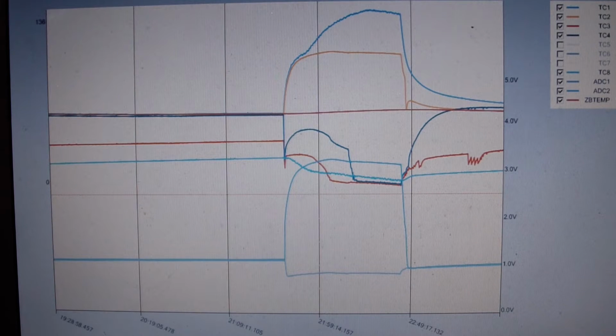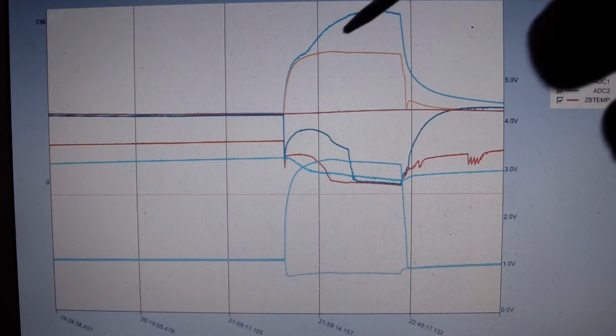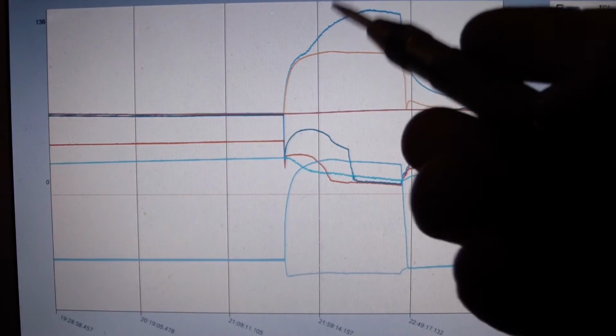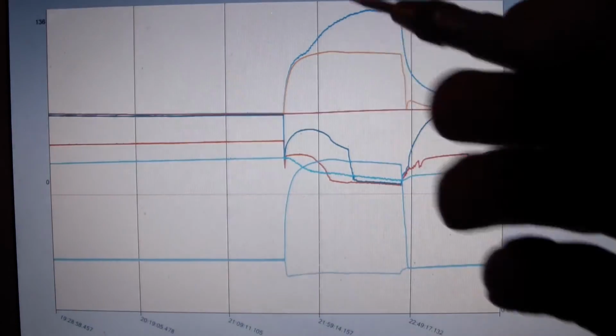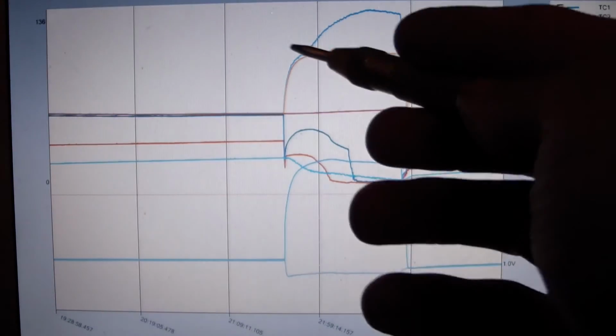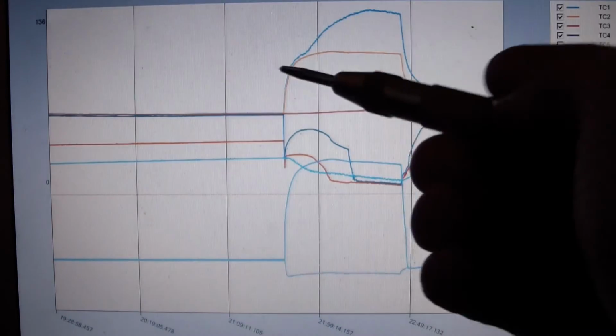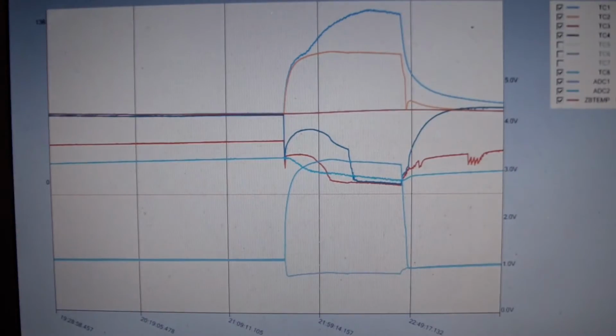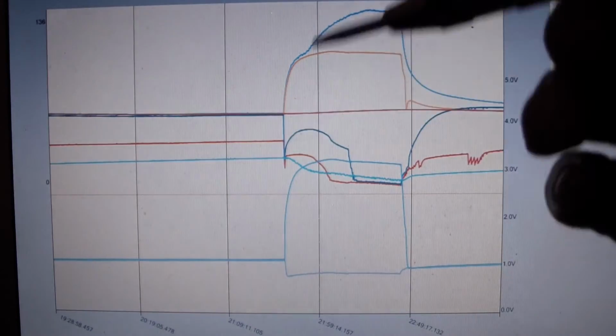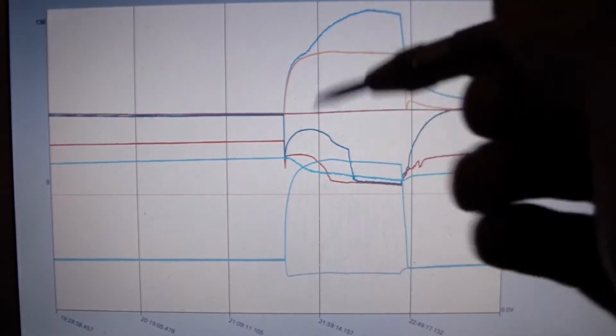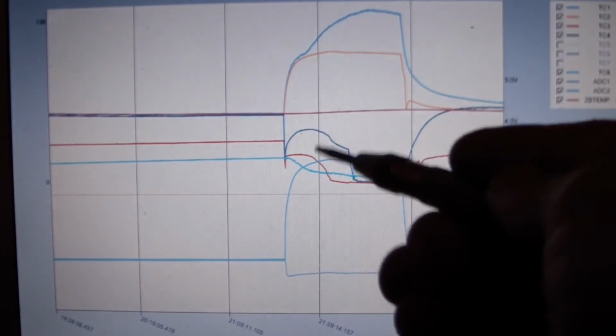I think that is probably the point where we're starting to get a liquid plug on the cap tube, and we're actually getting some condensation. Before this point, it's probably mostly just gas passing by the superheat thermocouple and the subcooling thermocouple, and that's probably why they're the same. From then on, we're probably actually getting some condensation occurring, which is going to leave a liquid plug at the cap tube. We're going to get more mass flow into the low side, which is going to better feed the low side.